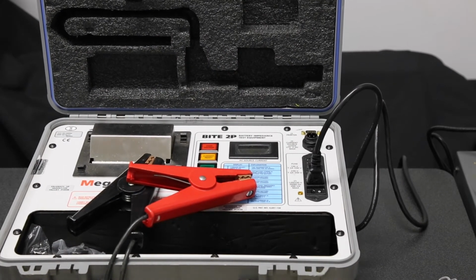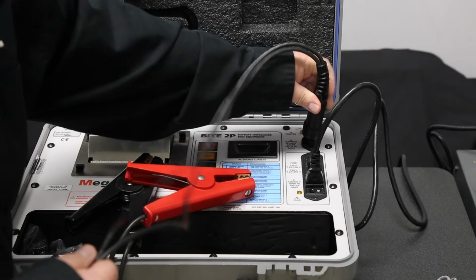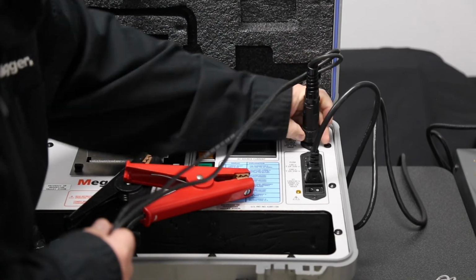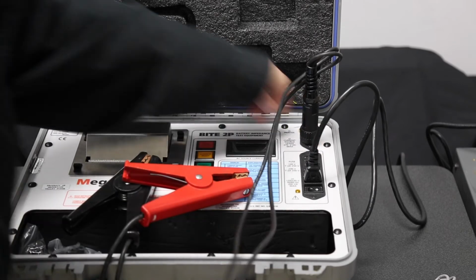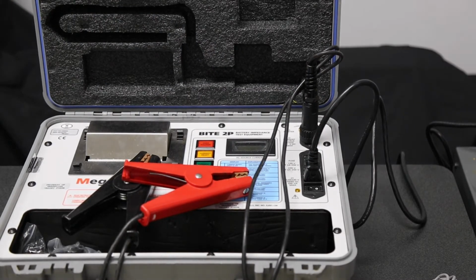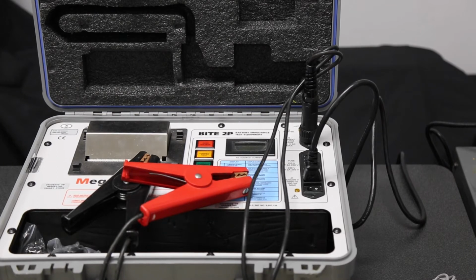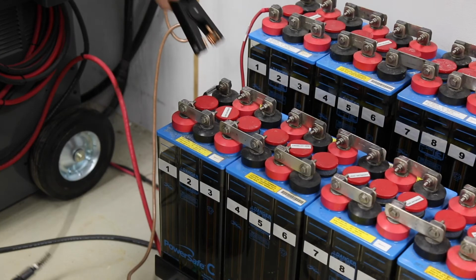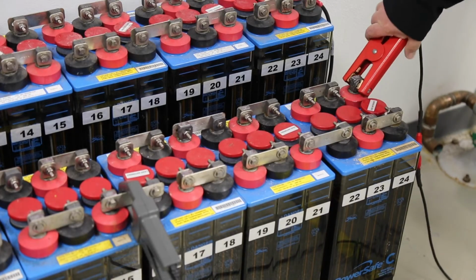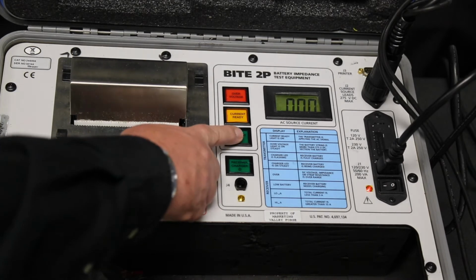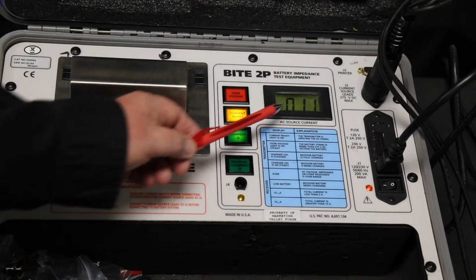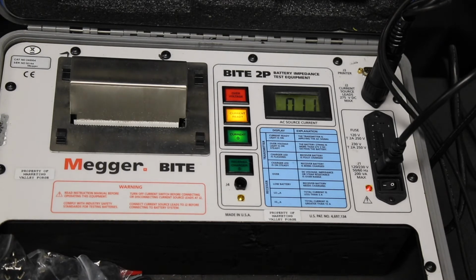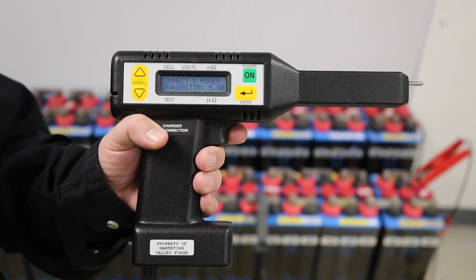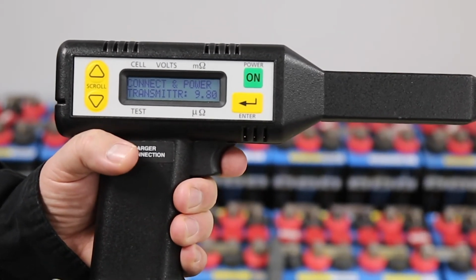So we connect the output lead to the transmitter. Now the transmitter can be connected across up to 275 volts DC. If the string voltage exceeds this, simply connect the transmitter across half the string at a time. We connect the transmitter across the string and turn it on, and also turn on the output. The internal coupling capacitor charges, then I get an output current. If I did not get an output current, this would be an indication of an open in the string. I can see the test current on my receiver, so I pull the trigger to save the value.